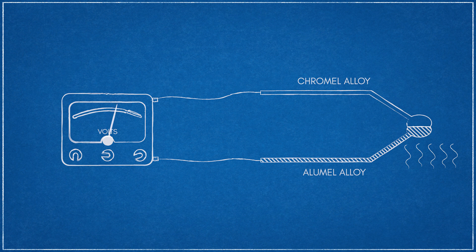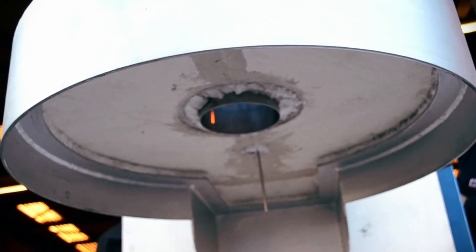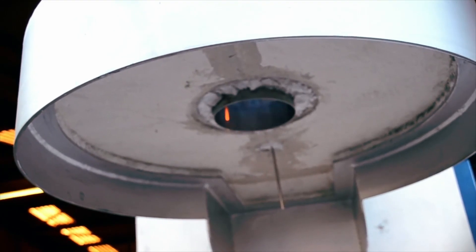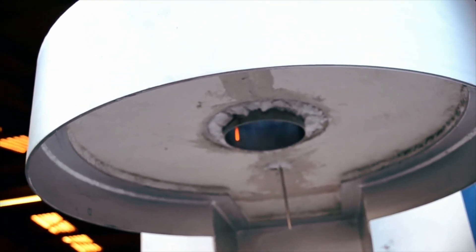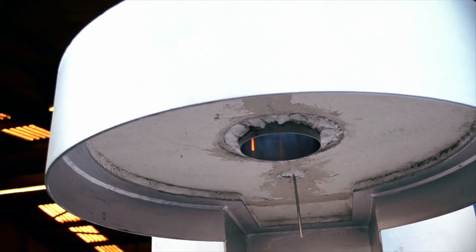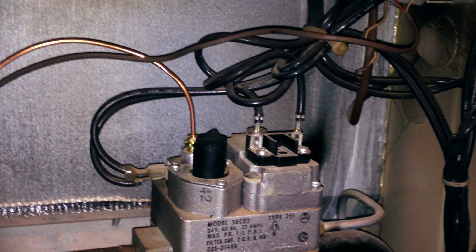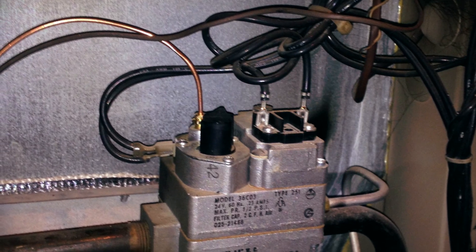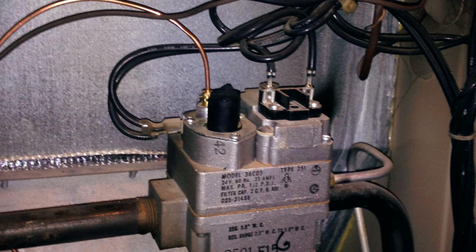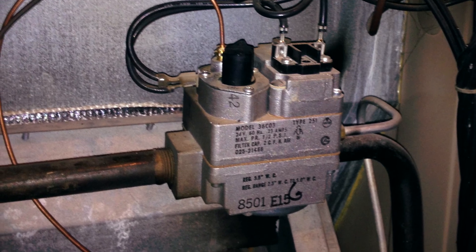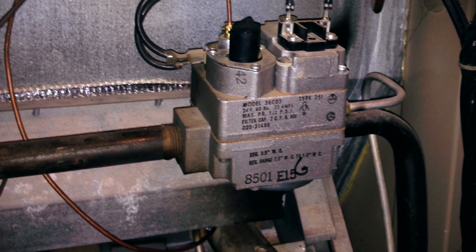Thermocouples are simple, rugged, inexpensive and interchangeable. Though they aren't precise, they are used as temperature sensors for both simple and digital control systems. They function well at temperature extremes that are impractical for other solutions, such as within direct flames. Because of their simplicity and ability to generate small amounts of electrical current, thermocouples are used even today in flame failure devices or flame supervision devices.